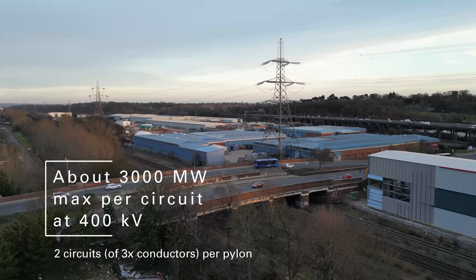L6s can, and usually do, carry quad cables at 275 or 400 kilovolts, giving roughly double the maximum power capacity of an L2 line. According to estimates in current National Grid planning documents, these are good for about 3,000 megawatts per circuit, and a pylon carries 2 circuits, so a single line of pylons could, in a pinch, transmit electricity to most of London.